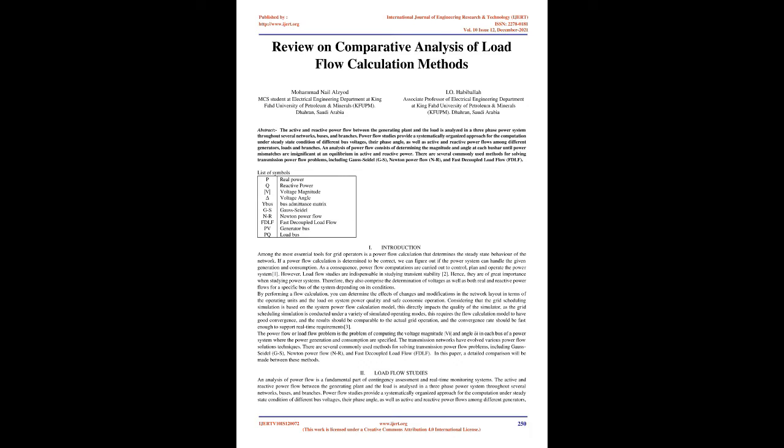During the planning and operation of power distribution systems, power flow analysis is widely used by professionals. Under load flow analysis, steady-state operation of a power system is analyzed to determine voltages at different buses, line flows in the network, and system losses — these are the outputs of the power flow model. This is accomplished by solving nodal power balance equations. Due to the non-linearity of these equations, iterative techniques are typically applied. An analysis of power flow consists of determining the magnitude and angle at each bus bar until power mismatches are insignificant at an equilibrium in active and reactive power.